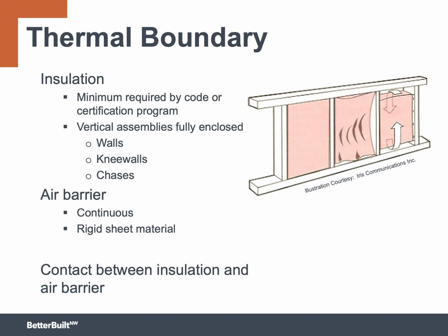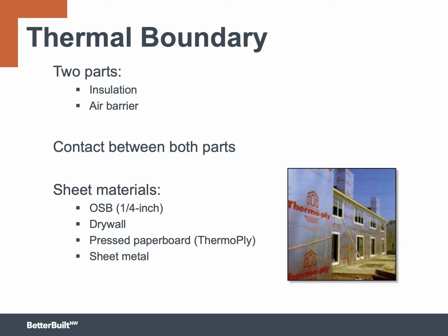You also have to make sure that the air barrier is continuous, that there are no gaps or holes. Continuity is essential. The air barrier must be made of a rigid material, one that won't flap in the wind. The materials that are most often used are drywall, oriented strand board, plywood, and there are pressed paper products called thermoply and energy brace that are also rigid. Those materials will cover the insulation and also prevent wind from intruding into the insulation. The thermal boundary has two parts, the insulation and the air barrier. Those things need to be touching each other, so the insulation is living in a six-sided box, where the insulation is touching all six sides of that box. And it's critically important on all the vertical applications such as walls.